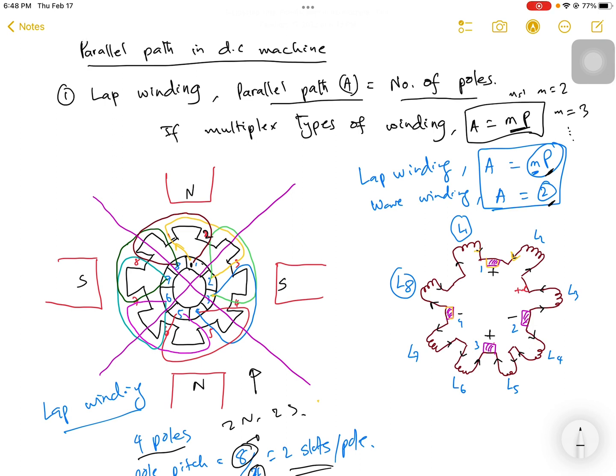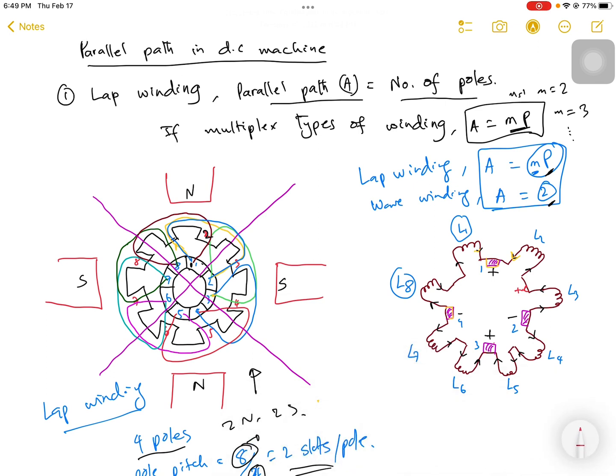Now let's start with commutator segment 1. The windings are already done beforehand. It starts from commutator segment 1, goes through the armature, and enters the next commutator section, ending at segment 2. Since this is lap winding, the next conductor starts where the first one ended — from commutator segment 2 — and then ends at commutator segment 3. From segment 3, another conductor passes through and ends at segment 4.